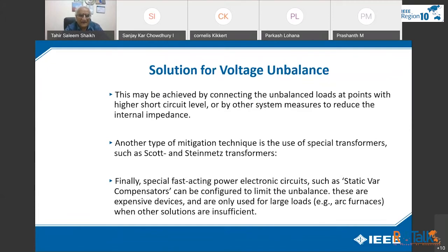Another type of mitigation technique is the use of special transformers, such as Scott and Steinmetz transformers. Finally, special fast-acting power electronic circuits, such as a static VAR compensator, can be configured to limit the unbalance. These are expensive devices and only used for large loads, for example arc furnaces, when other solutions are insufficient. VAR capacitors are used on the transmission lines.